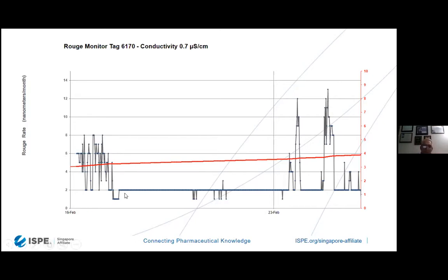So what happens over here is as we're doing filling operations and usages, the rouge rate is very small. When we turn off the point of use, the rouge rate goes up once again. And when the rouge rate goes down again, it's because we open up a point of use or a collection point to take a microbial sample, as an example. When they close off the microbial sample, the rouge rate goes back up until they open another point. So when you think about this, this is actually very simple.